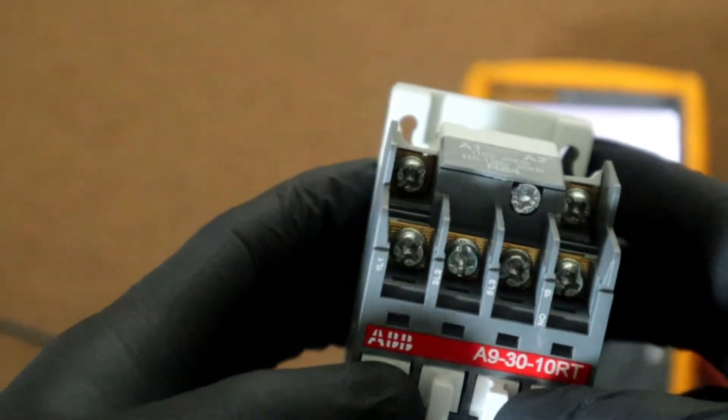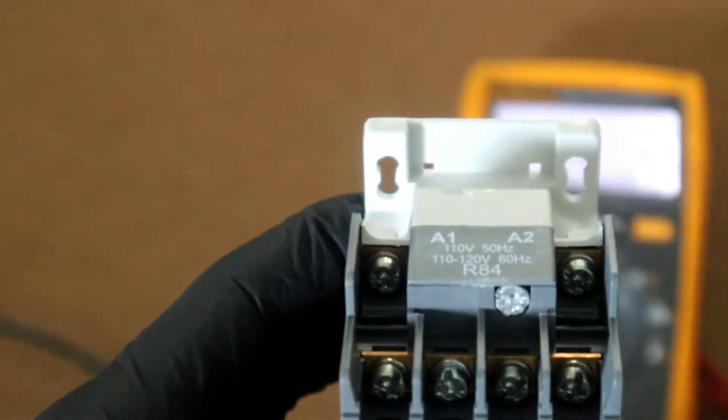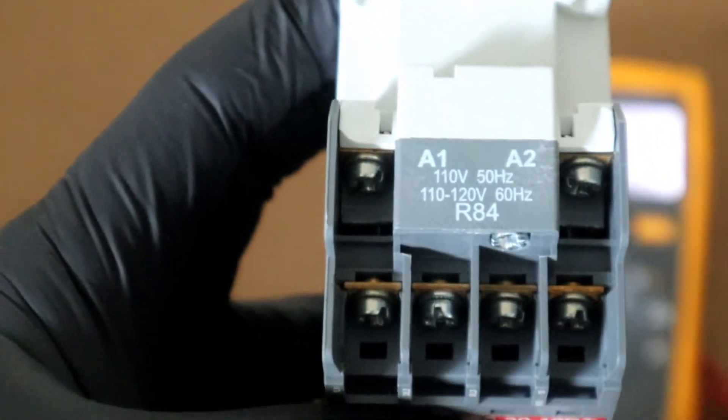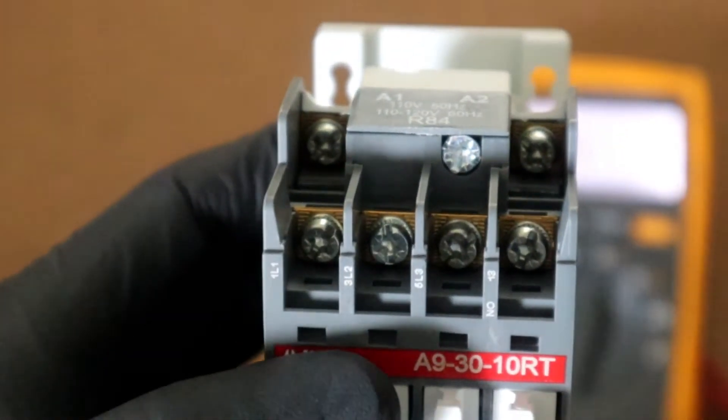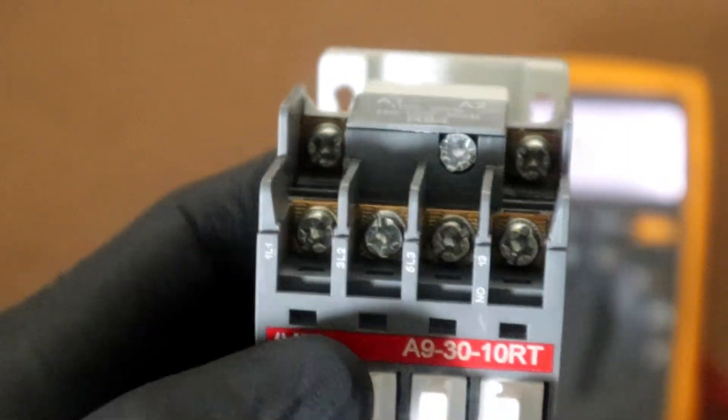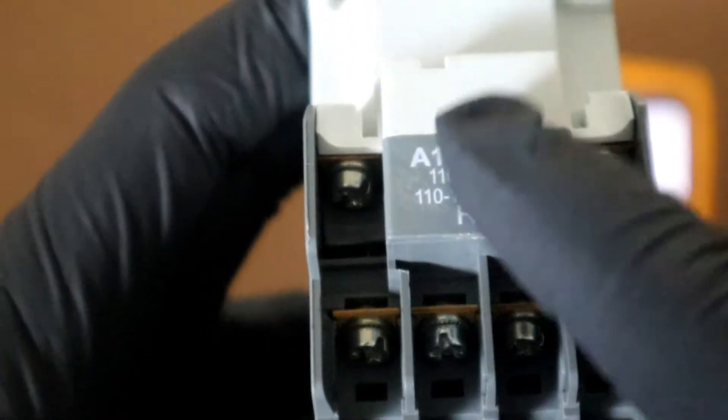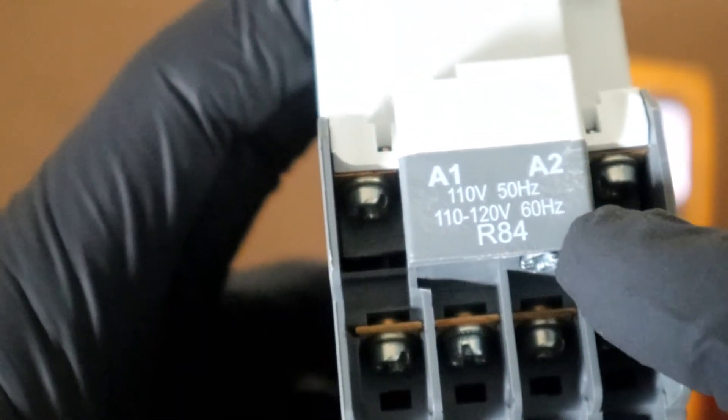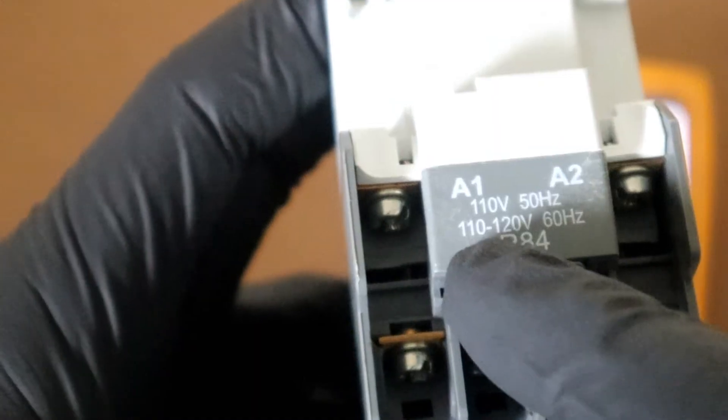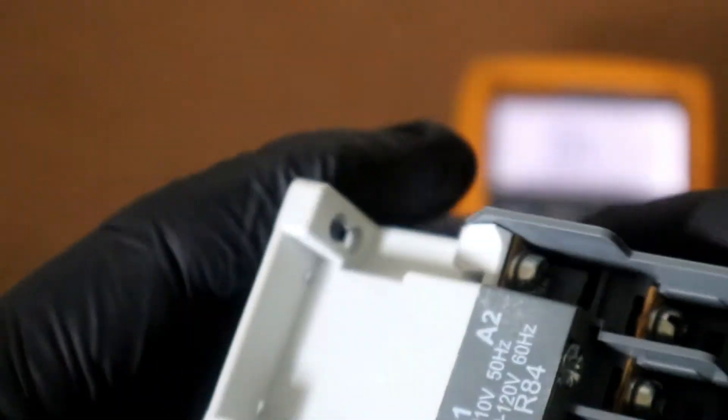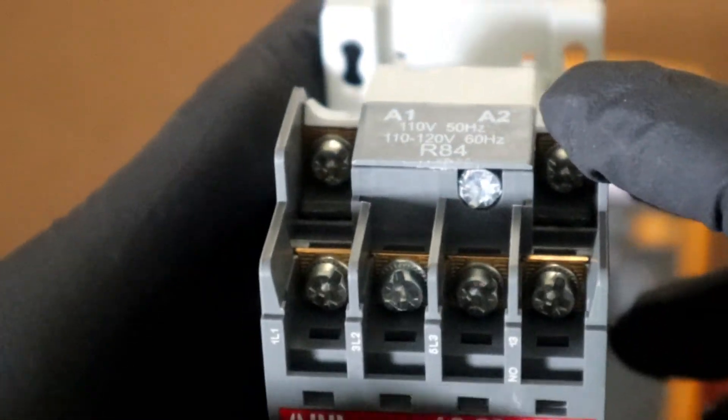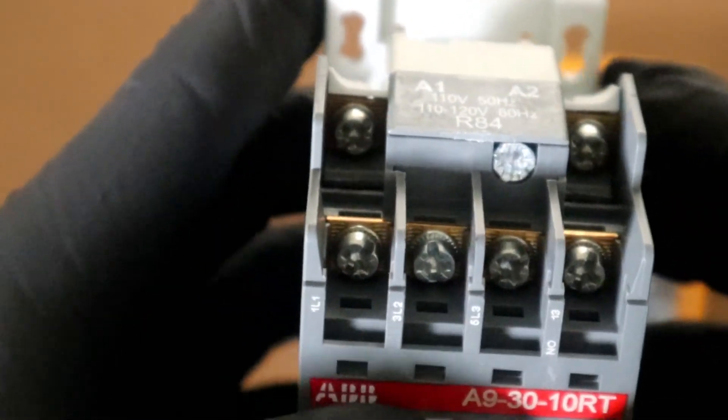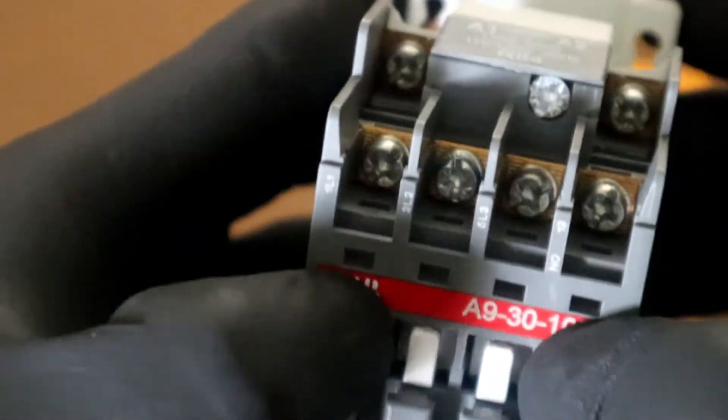The final step to conclude our contactor testing is testing the coil, A1, A2 section. The coil acts as the switching mechanism for a contactor. This coil is 110 volts 50 Hertz operated or it can be operated on 110 to 120 volts 60 Hertz. When our voltage is applied across our coil A1 to A2, there is an electromagnet inside which pulls our contact in.